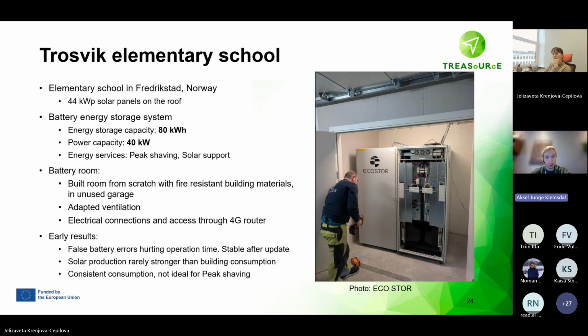This system has run for about a year now, and the report isn't finished. Early results show some issues with battery errors, which we now know were false but still required careful troubleshooting, hurting operation time. Solar production isn't that strong, so we've only been able to use solar for some days out of the year. Consumption here is also rather flat, whereas the ideal case for peak shaving is a lot of variation with high, short-lived peaks.